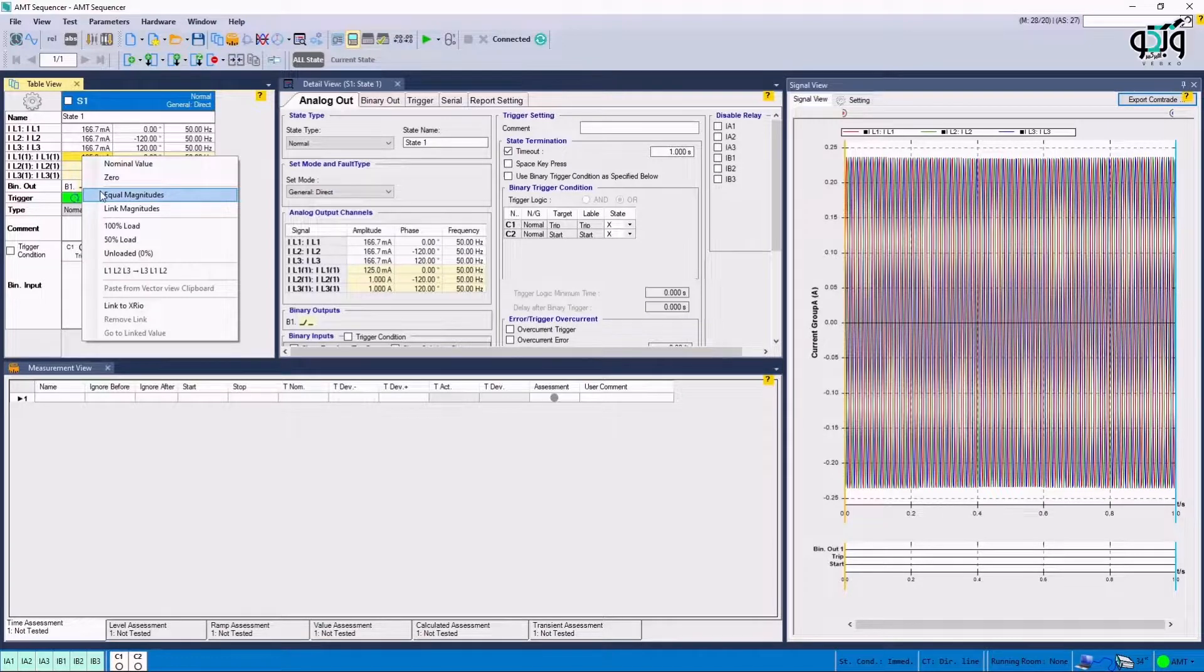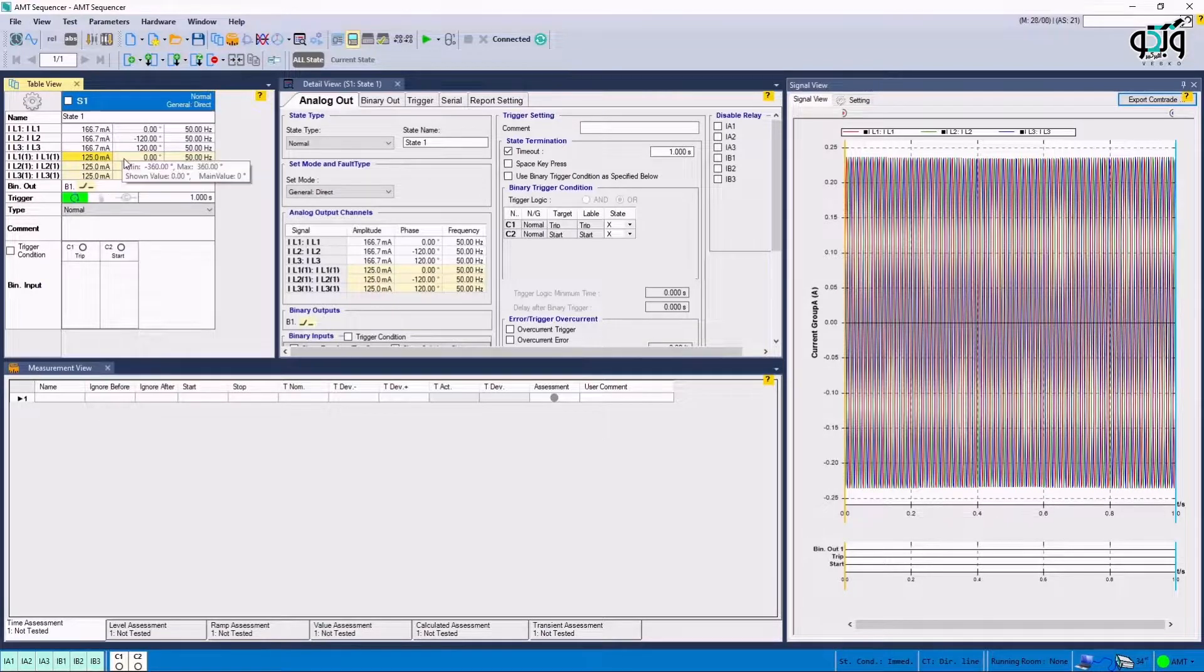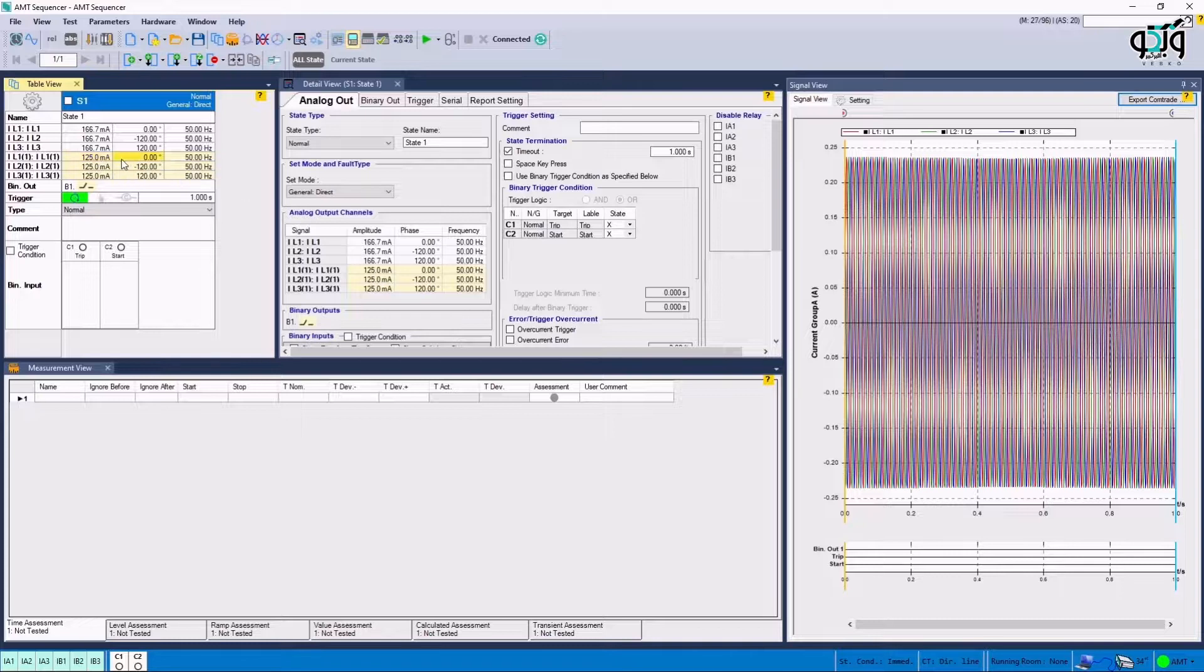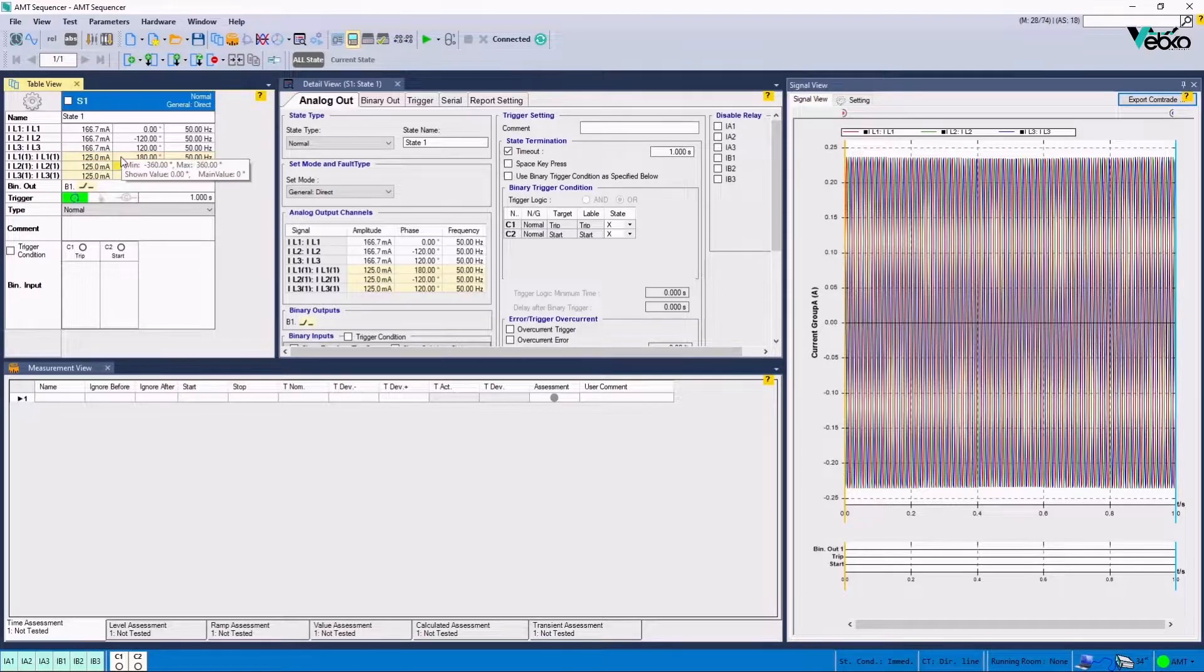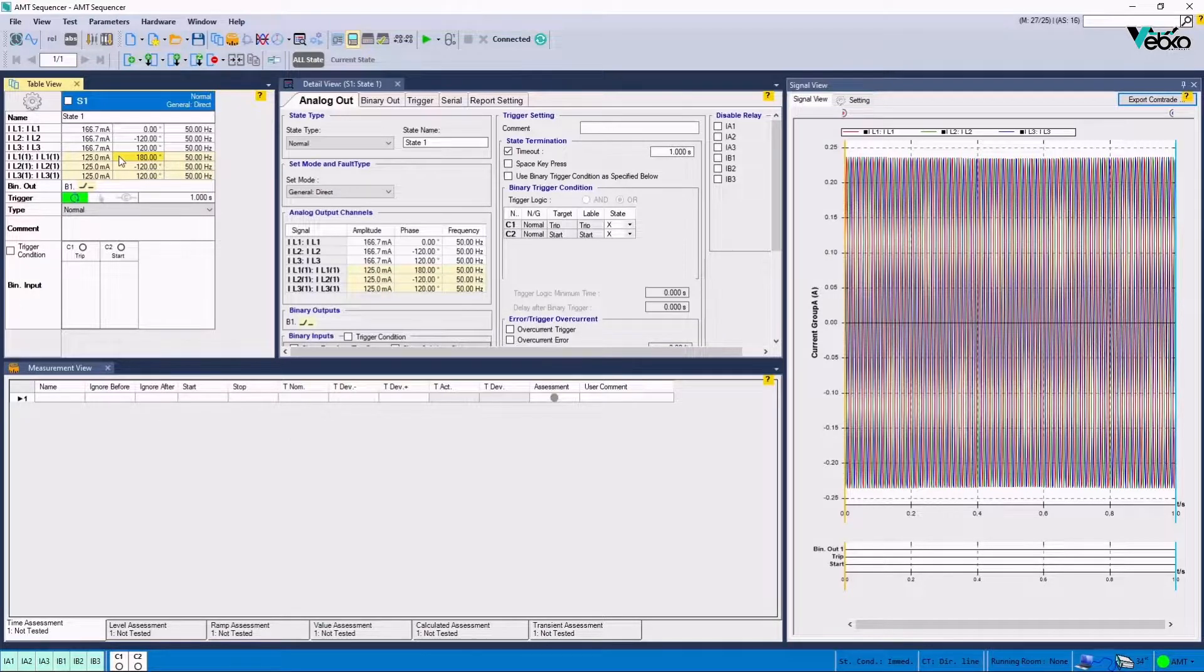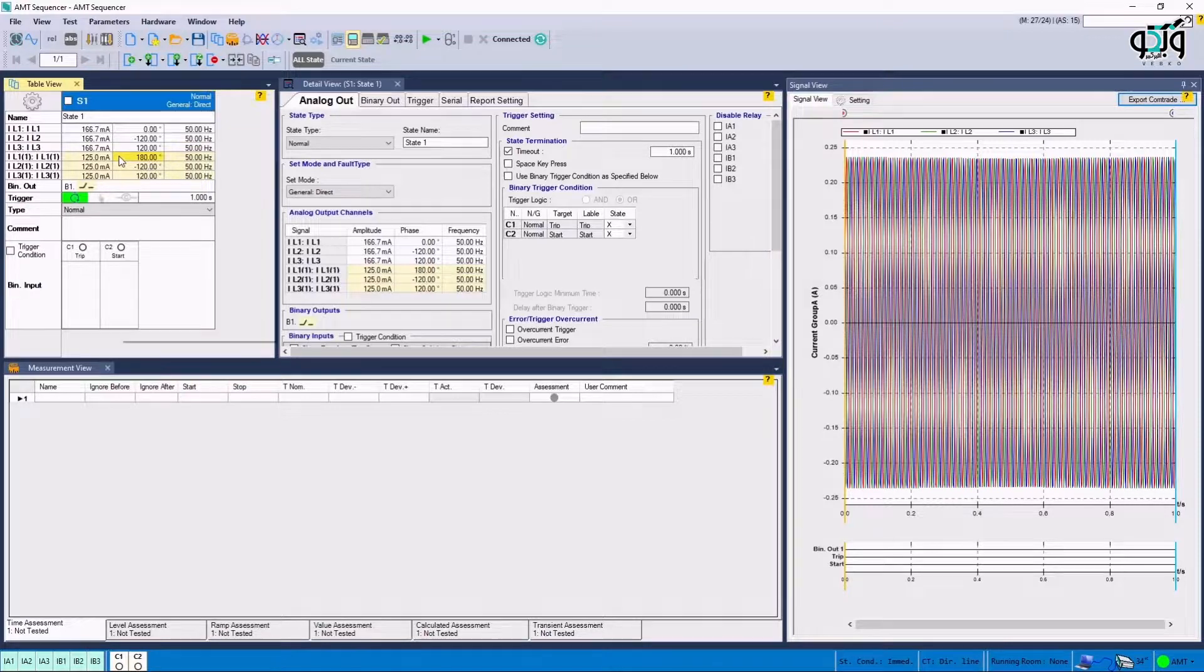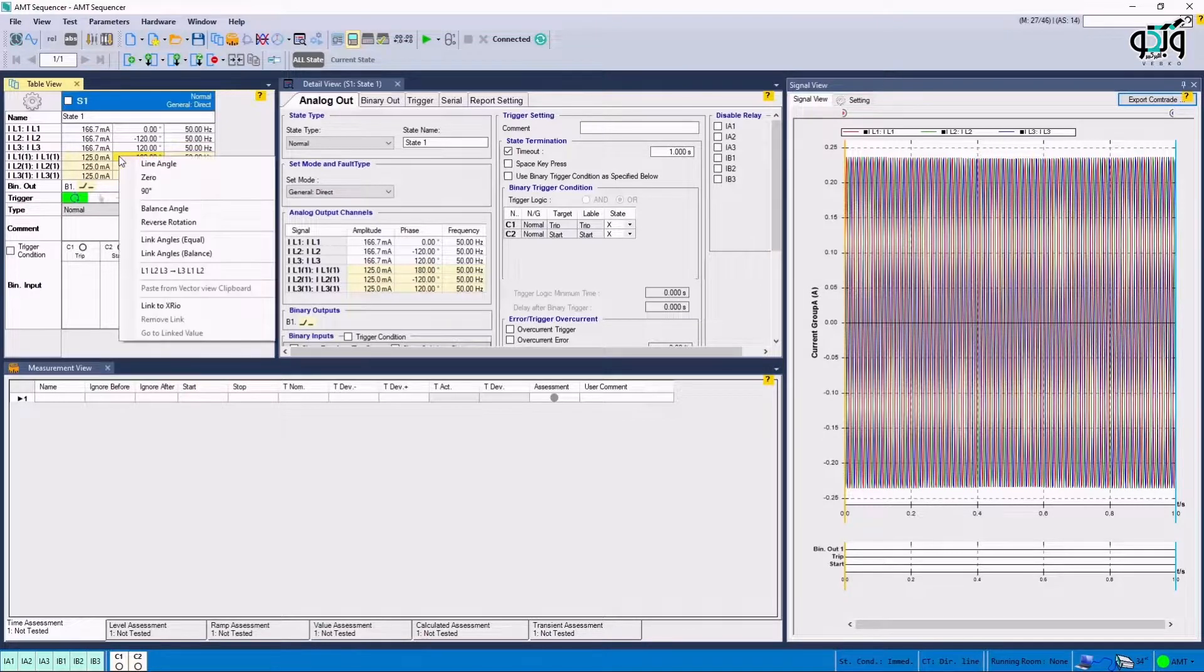By entering a value in a cell and right-clicking on it, and then selecting Equal Magnitudes option, it is possible to enter the same value in all cells of a current injection site, then the same process can be repeated for the other side. Now, since during a stability test, the currents on both sides need to be equal in accordance with the CT turns ratio and have a 180 degree difference, the currents from one side are taken as the bias, and a 180 degree difference is considered for currents from the other side.